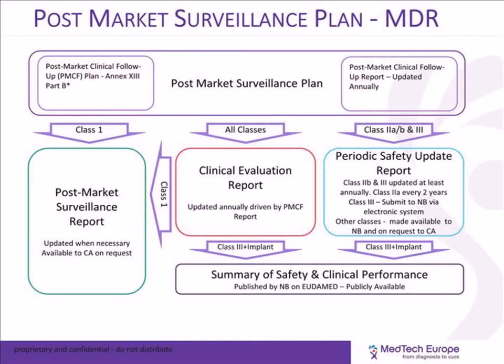Now, if you deal with higher class device, such as class 2, class 3, or implants, then you need a periodic safety update report, which is to be loaded into EUDAMED. And we'll drill a bit on that in the next few slides. For high-risk device as well, class 2, class 3, you also need a summary of safety and performance, which is published in EUDAMED and available to the general public. So this gives just a broad overview of the universe of these reports.